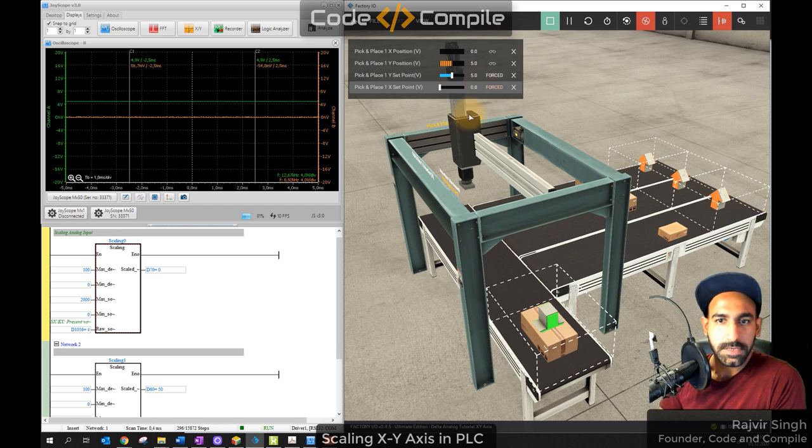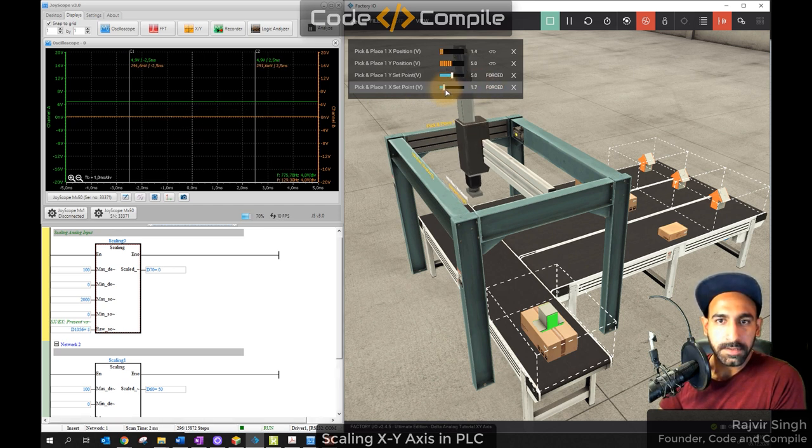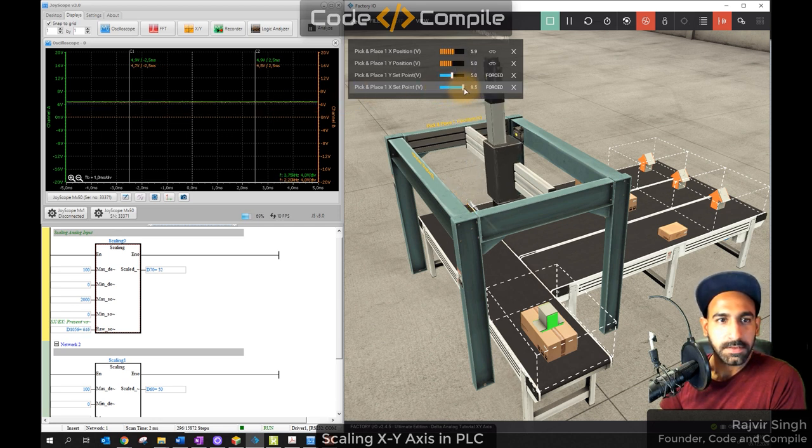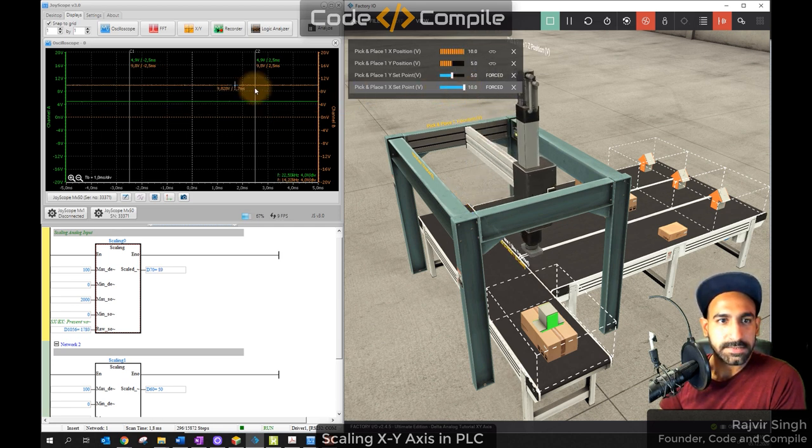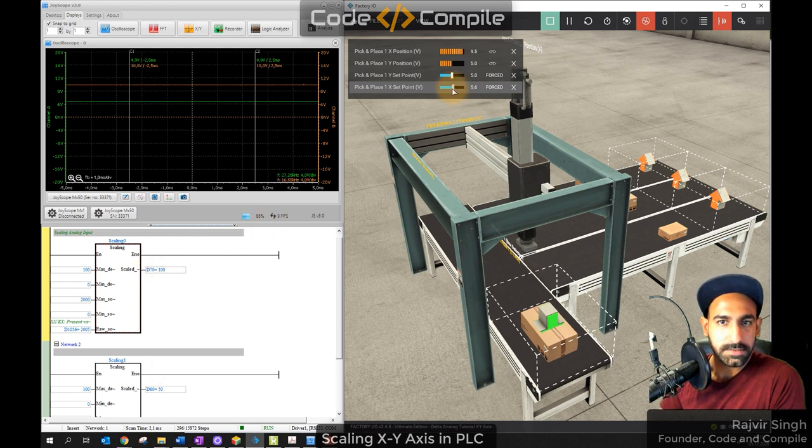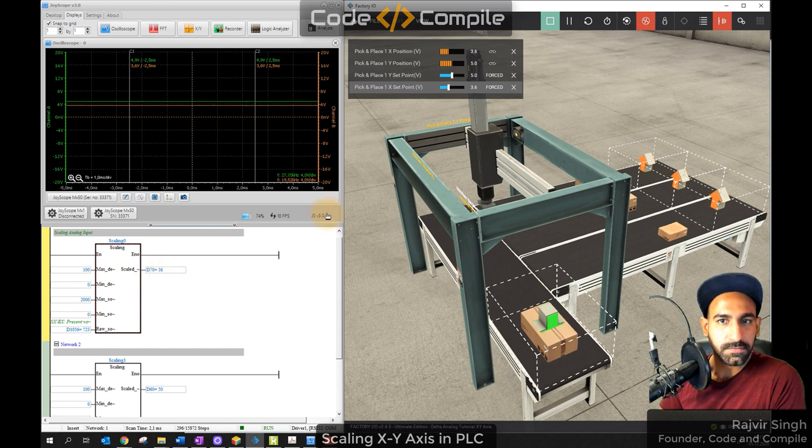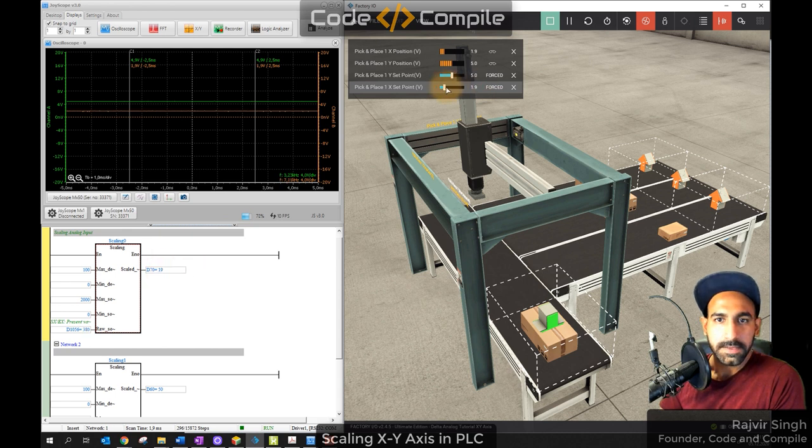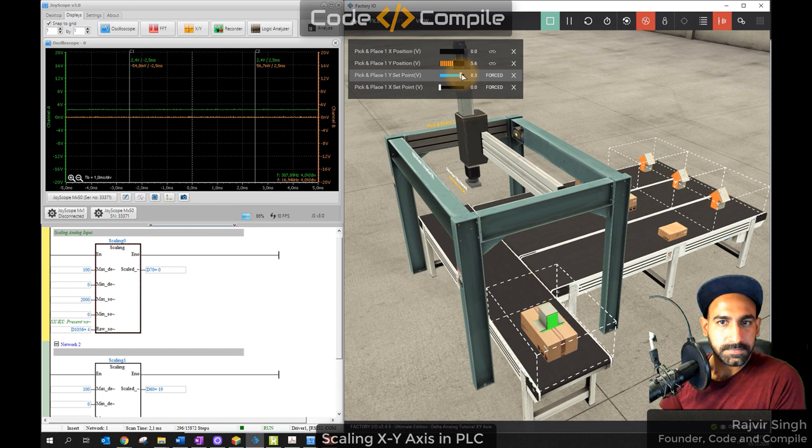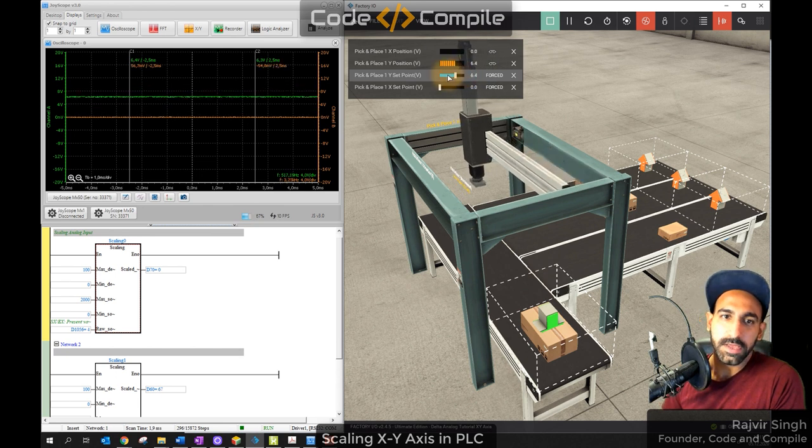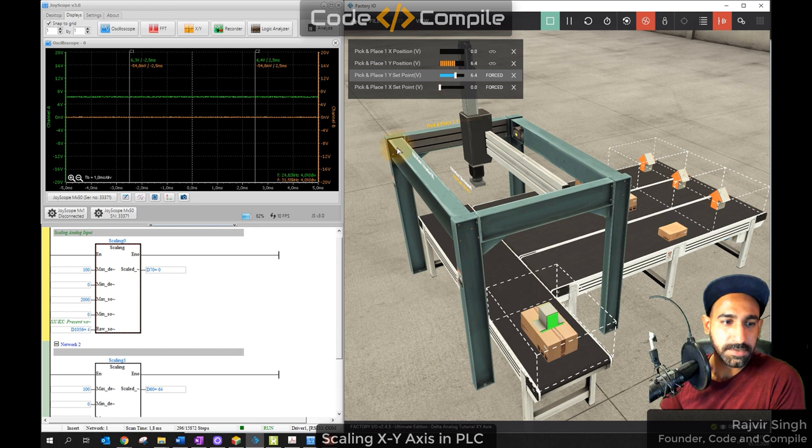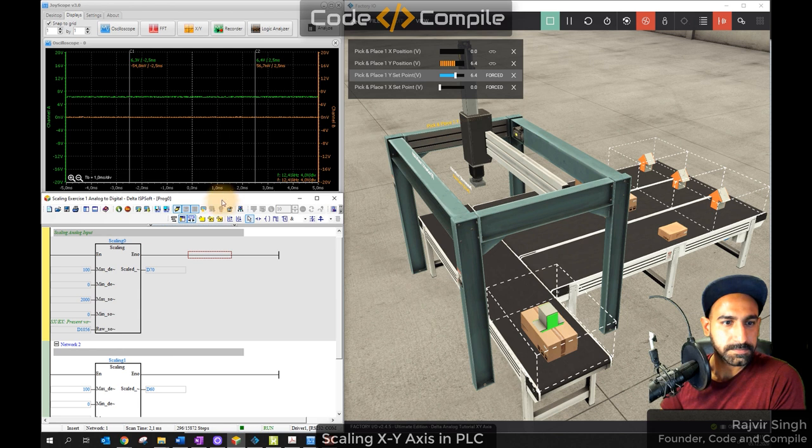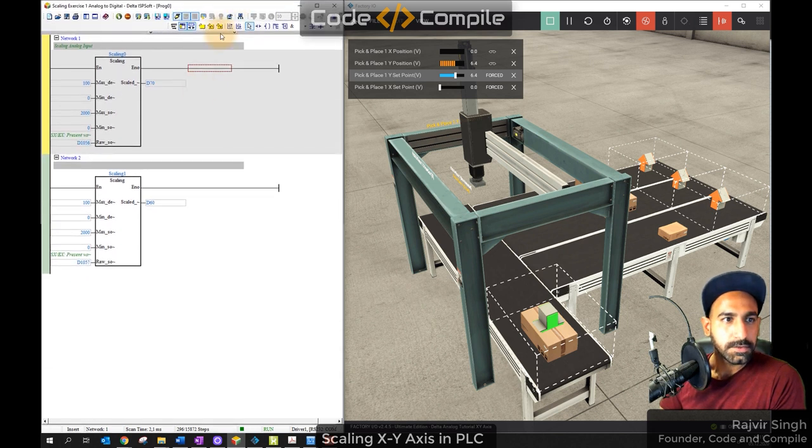So I have two channels, channel CH0 and CH1. This is zero, so this is zero volts. And this is increasing, now it's 1.679. So this is X-axis feedback and X-axis here we can see hundred. Now it's 41, 36, and keep on reducing, 19. Similarly, Y-axis is like this. So how do we get X-Y axis feedback in PLC? Now we are going to get the percentage, so here we are going to use the formula.